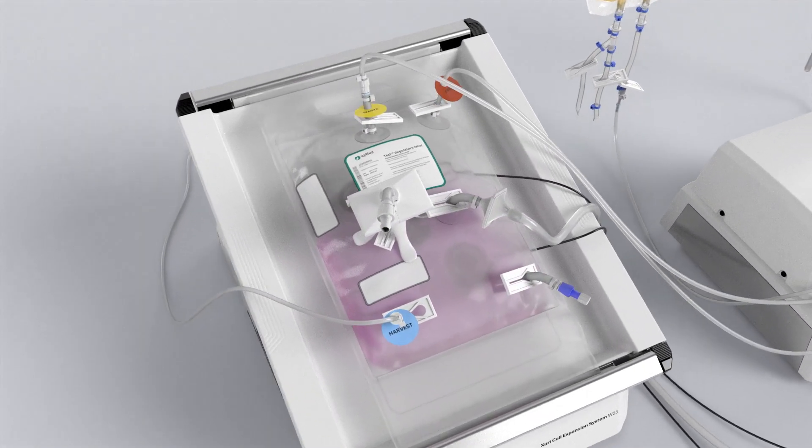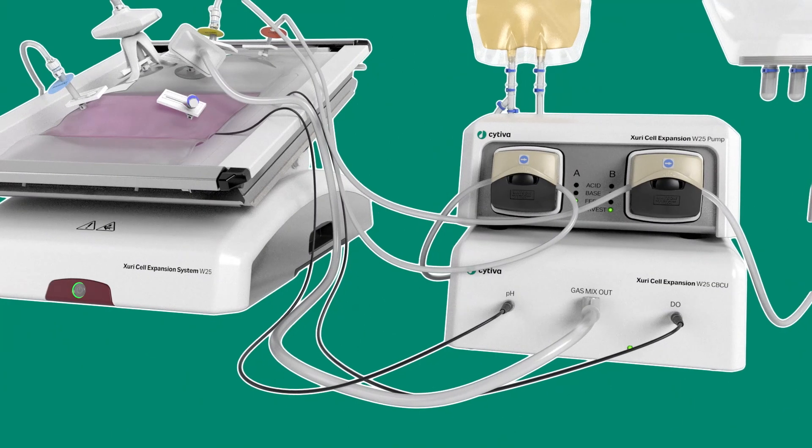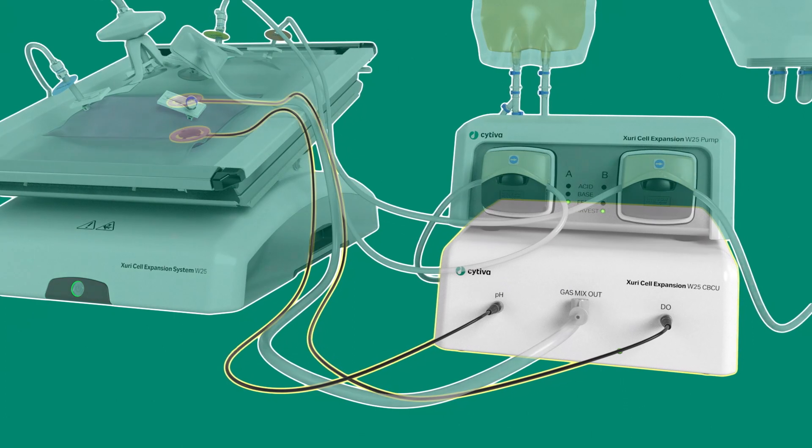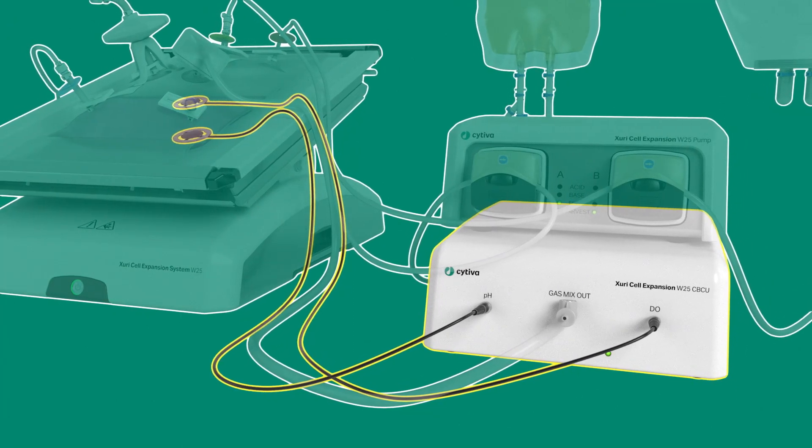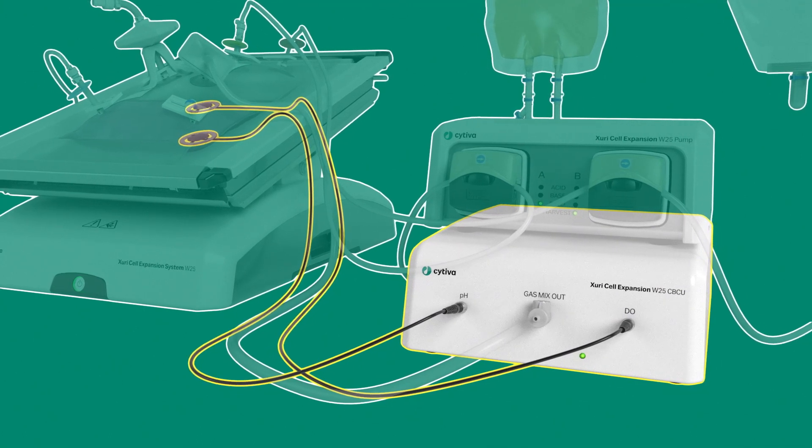Our cell bag bioreactor includes single-use optical spot sensors for measuring pH and dissolved oxygen. They're specifically designed to provide the high accuracy and process control you need. To measure pH and dissolved oxygen, you'll need a gas mixer and fiber optic cables designed for use with the Xuri system.